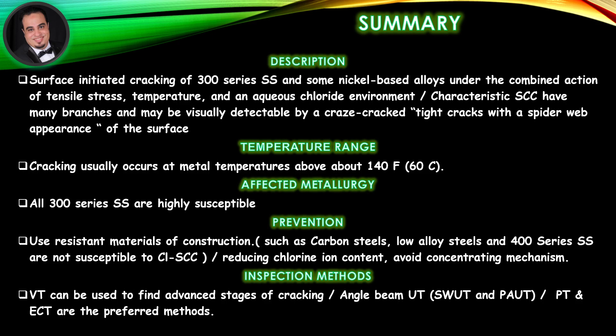Prevention: Use resistant materials of construction such as carbon steels, low alloy steels, and 400 series stainless steel, which are not susceptible to chloride stress corrosion cracking. Reduce chlorine ion content and avoid concentrating mechanisms. Inspection methods: VT can be used to find advanced stages of cracking; angle beam UT, SWUT, and PAUT, as well as PT and ECT, are the preferred methods.